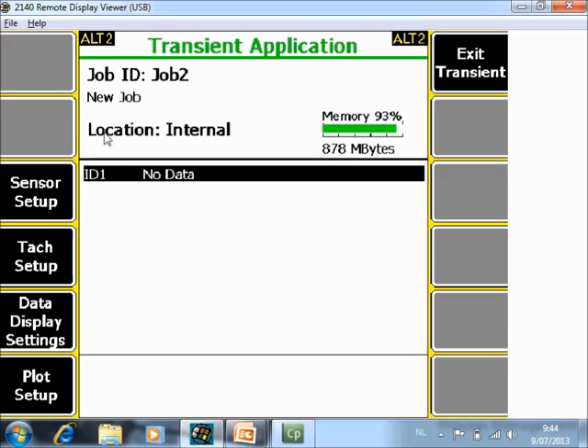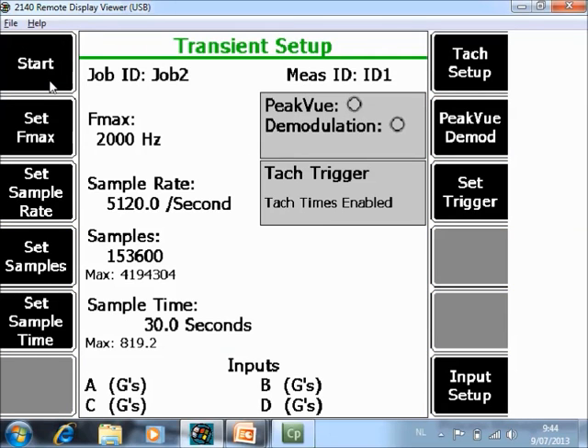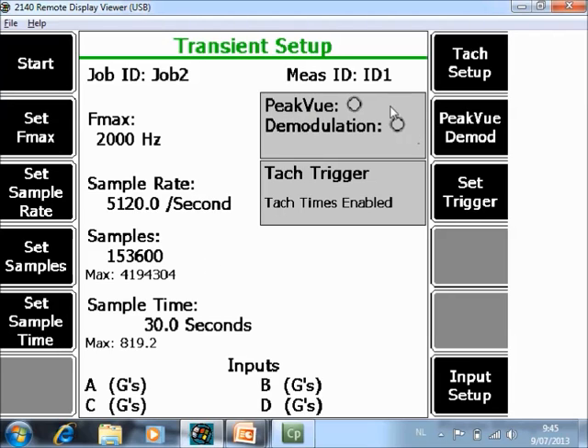I'm ready with the one-time settings. I can go to my settings for this particular job, so I go back to Alt 1. In Alt 1, I go to setup acquire data. First of all, I specify that I want to measure, for example, till 2000 Hz. And here I specify how long I want to measure, for example 30 seconds. Those 2 numbers are coming in automatically if you modify the Fmax and the set sample time. I don't activate PeakVue or demodulation.